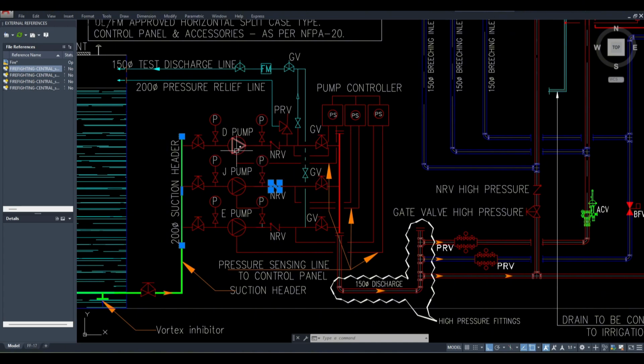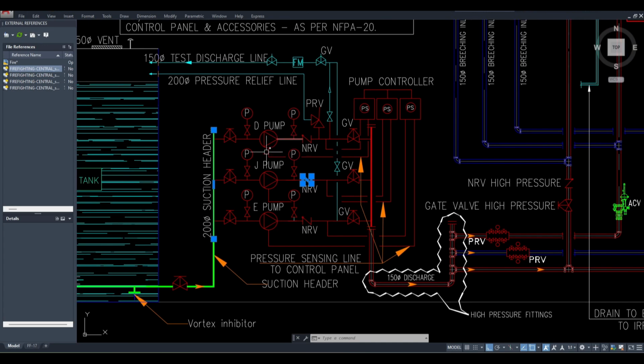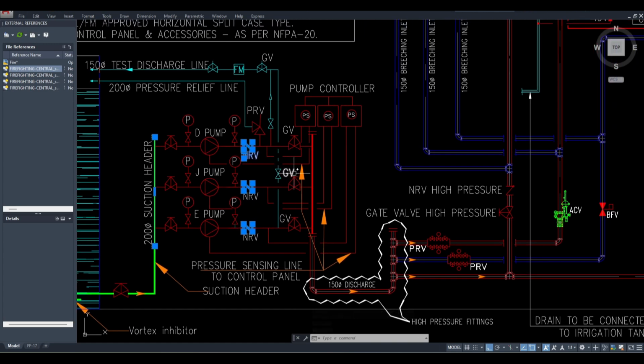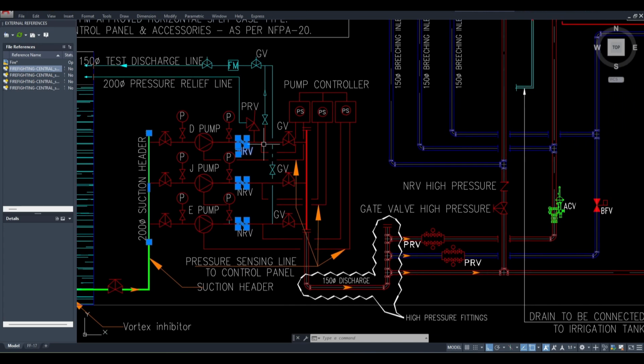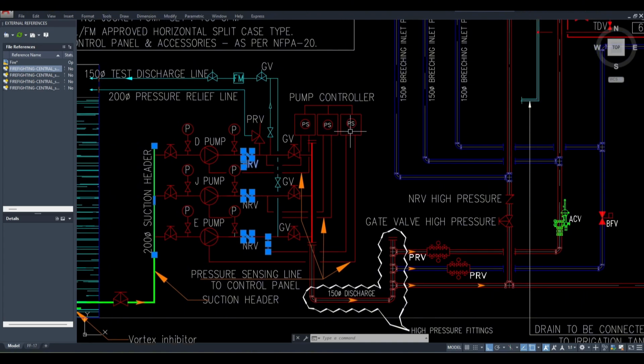Okay. So basically we want to stop this here. So that's why NRV is always provided on the front side of the pump, so that we can protect the equipment and we can keep the pressure inside the line. Simple. So if any pump is connected without NRV, then you can immediately comment that your system is not correct. The NRVs are missing here. Okay. Then all these lines go after the NRV, only this pressure sensing line. This line we call the pressure sensing line, which is a small pipeline which goes to the pressure sensor here, which is kept in your control panel.